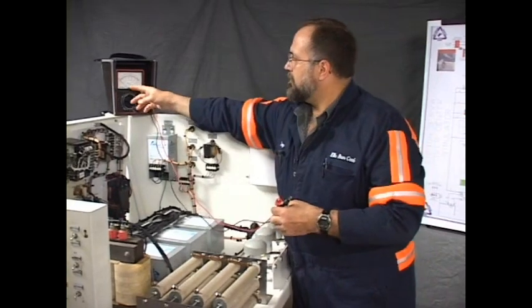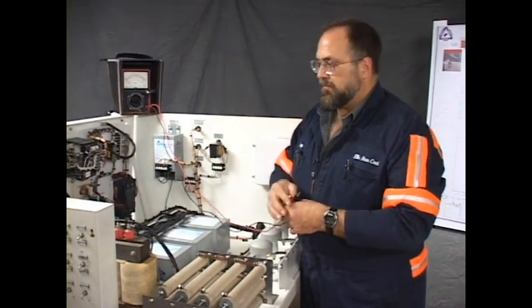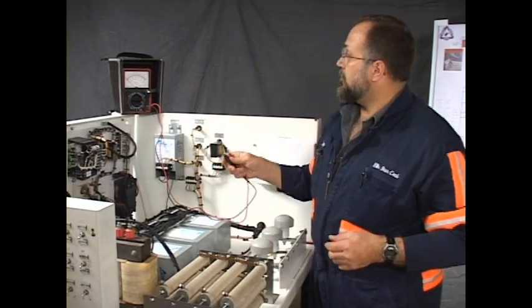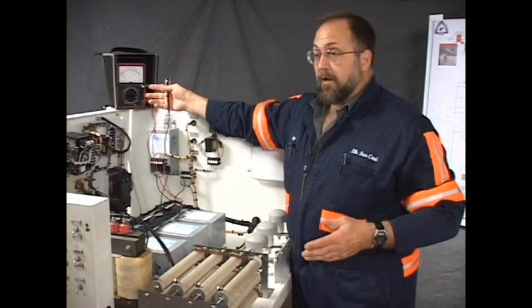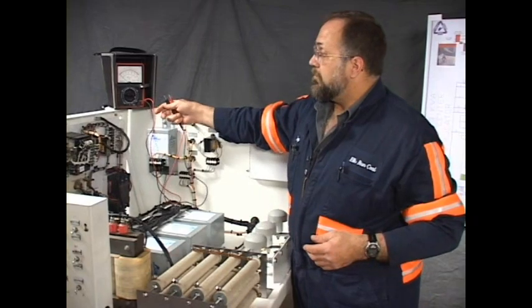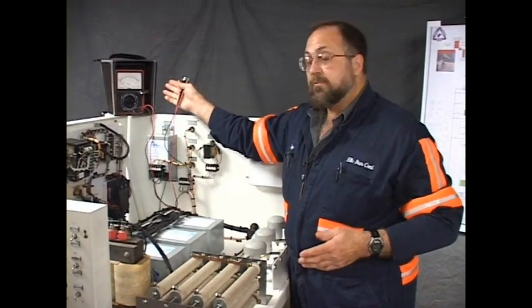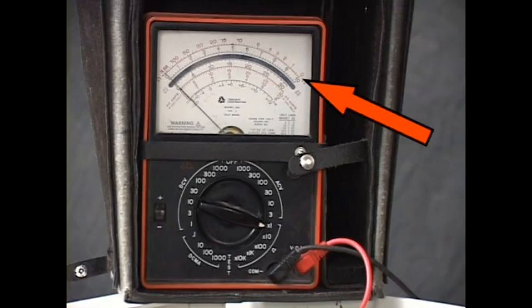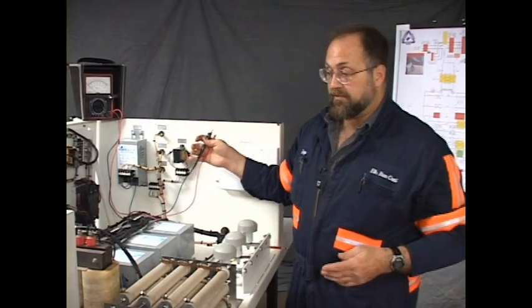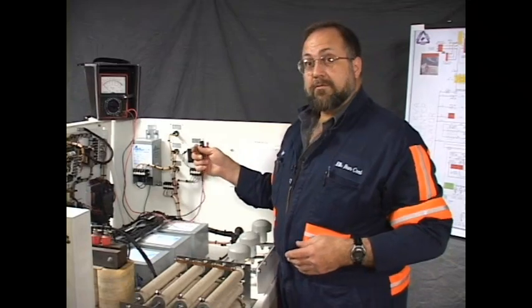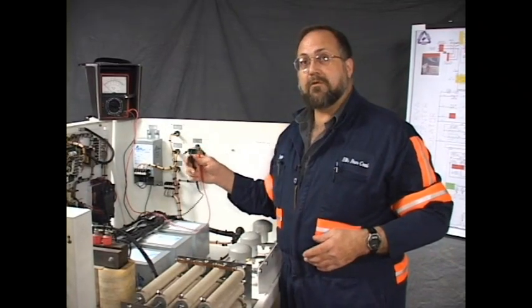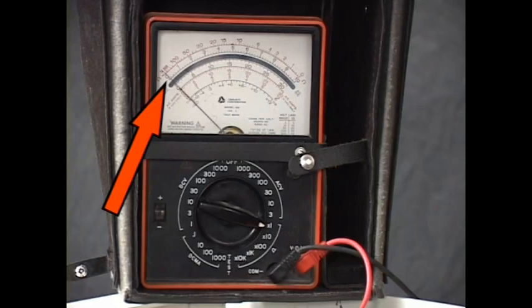Keep in mind the ohm meter reads exactly in reverse to virtually every other analog instrument that you'll read in your life. On your speedometer, on your gas gauge, on most everything you read, the farther the needle swings to the right, the more you have. On an ohm meter, 0 is on the right. You're measuring resistance, how much resistance you have. The more resistance you have, the poorer the circuit is. Okay, the more opposition to the flow of current. A needle that stays on the left indicates an open circuit or an infinite amount of cable resistance.